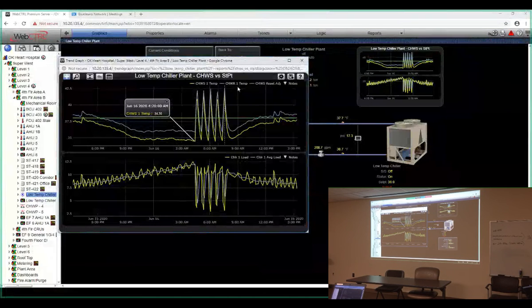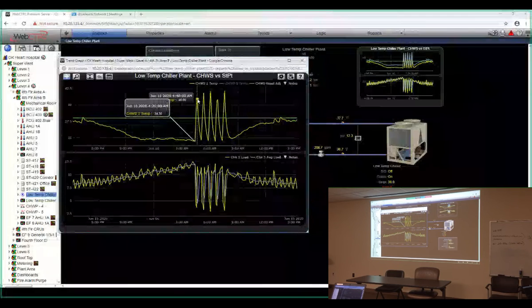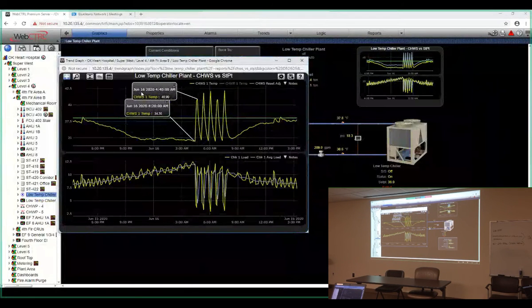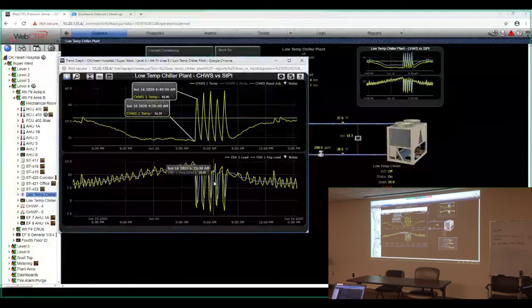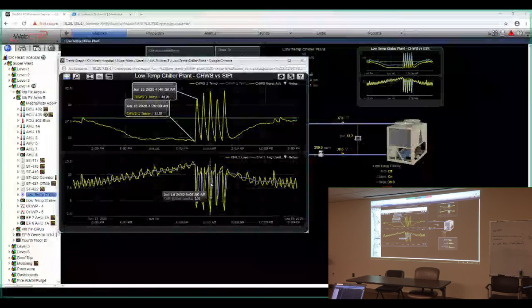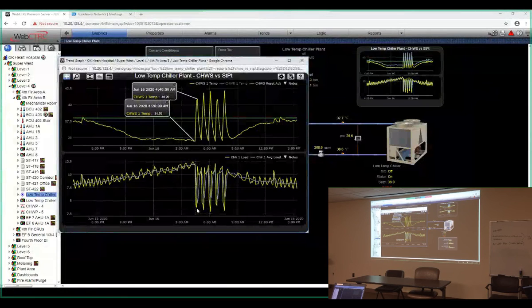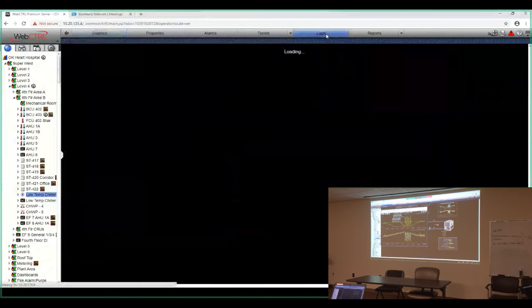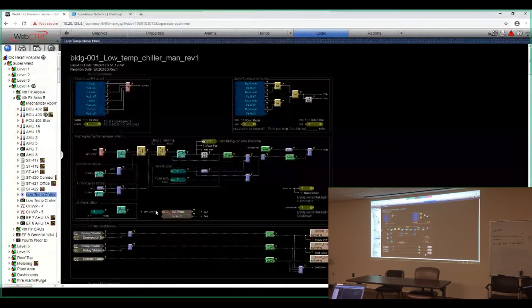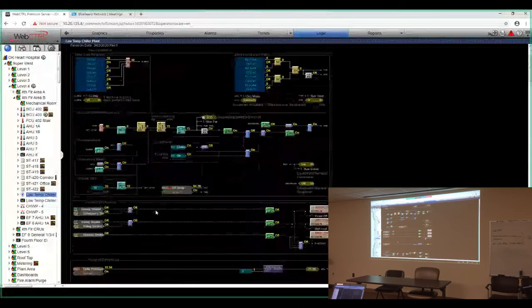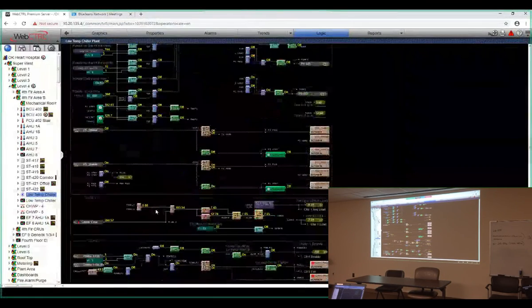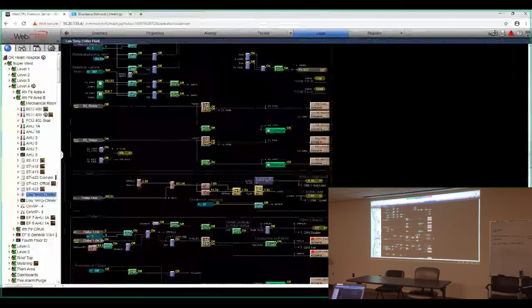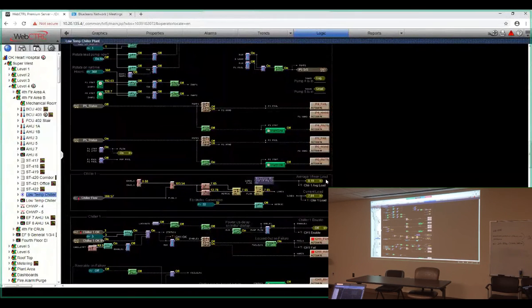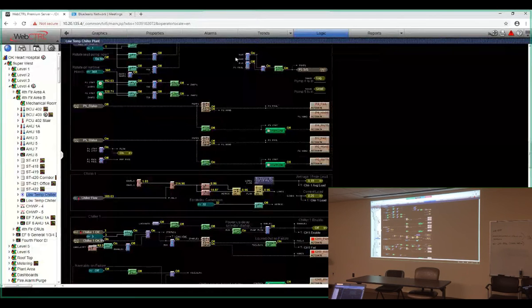You can turn off the blue one, click on it, yeah. So the load, is that a percentage? That load is tons. Tonnage? Yeah. Can we look at the logic for a minute and see what that load is calculated on? If you look back on June 14th, it did the same thing at 3 a.m. Scroll down. Two days ago? It's doing the same thing on the 13th, exact same time. Same thing on the 12th, exact same time. Yep.